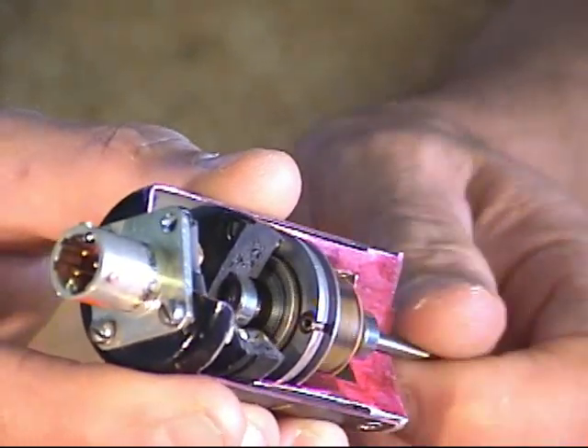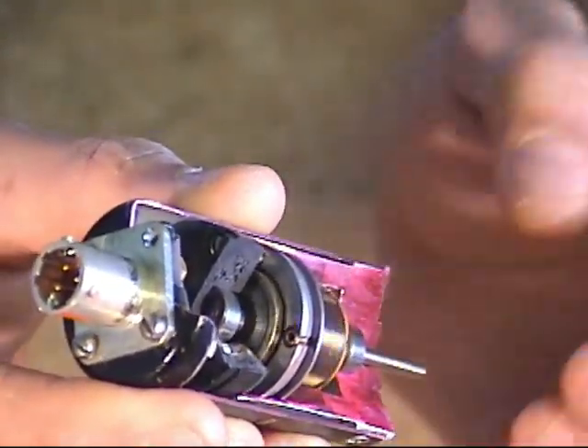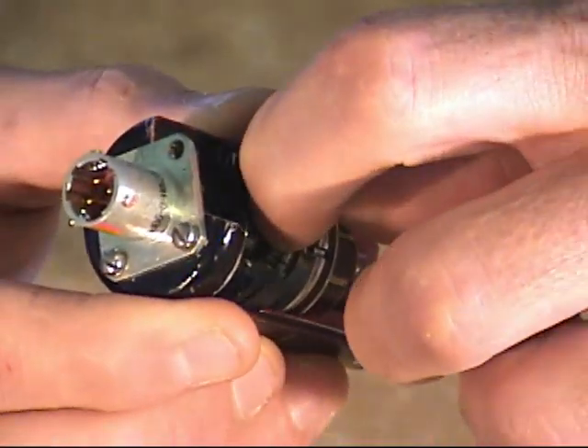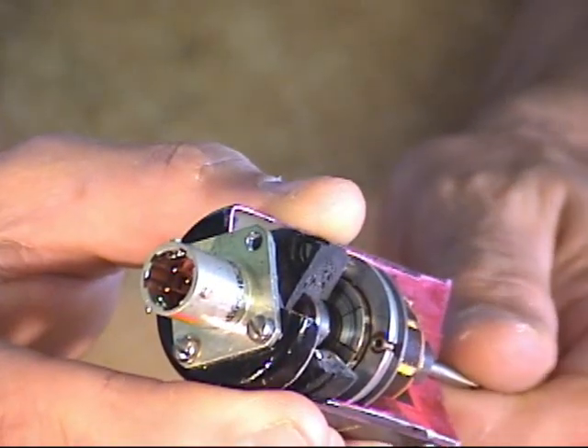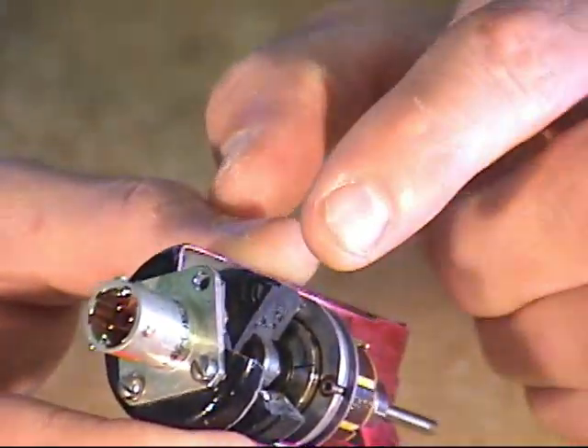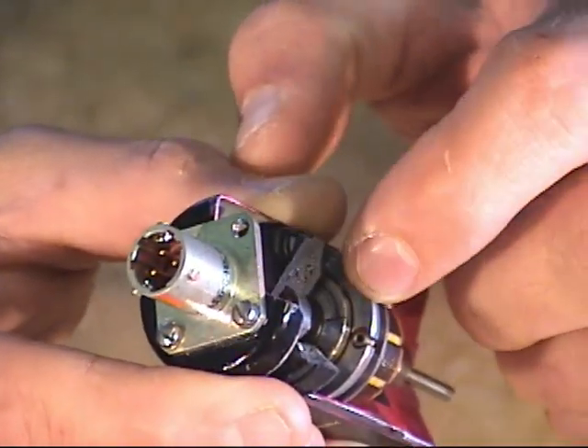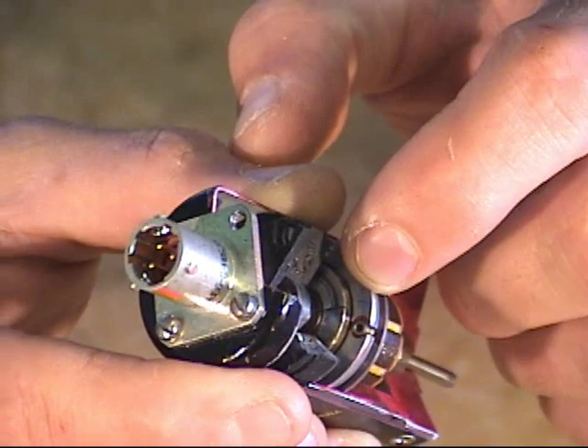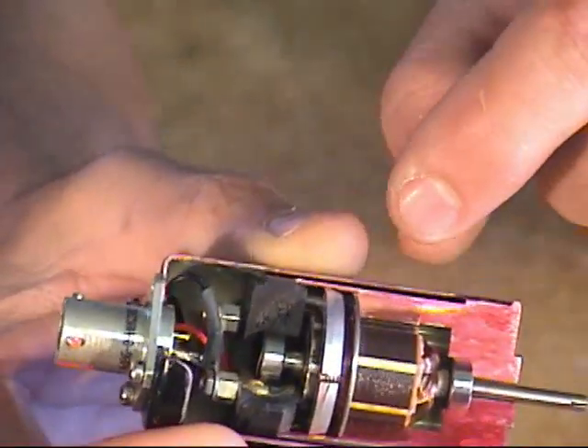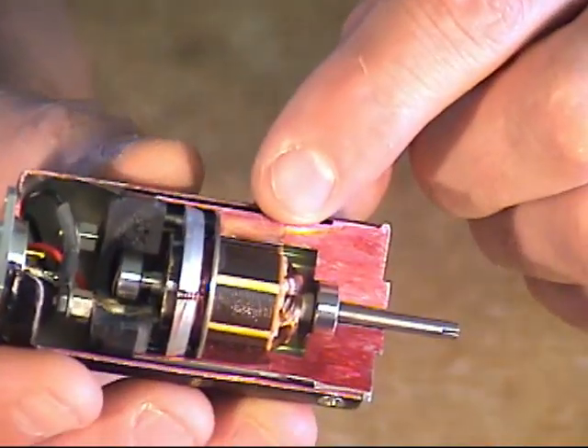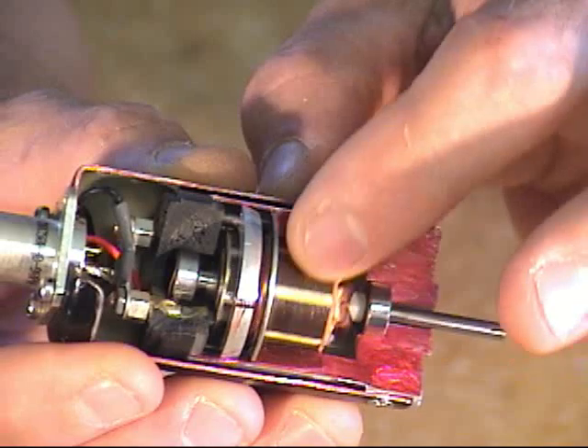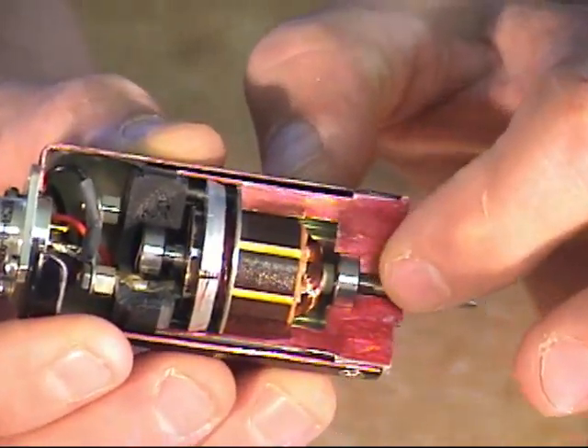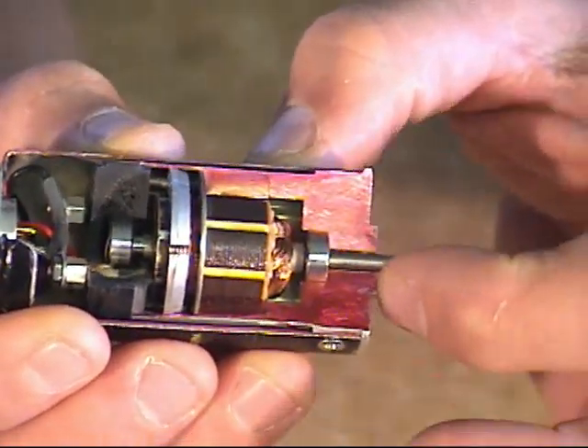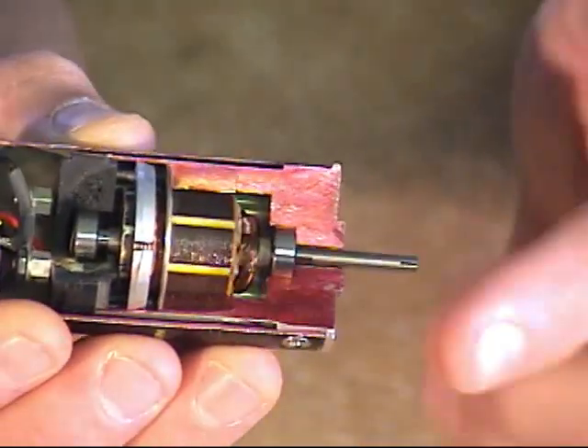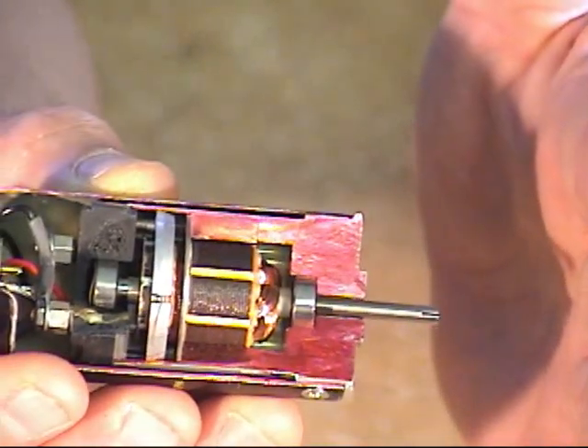The commutator spins, the brushes deposit a black film on the armature, and that buildup of film is one of the things that contributes to resistance between the brushes and the commutator. Typical permanent magnet DC motor here. Permanent magnets on the outside, windings on the inside. Notice there is no moisture seal on the front of the unit here. Water's free to ingress from the hubcap side.